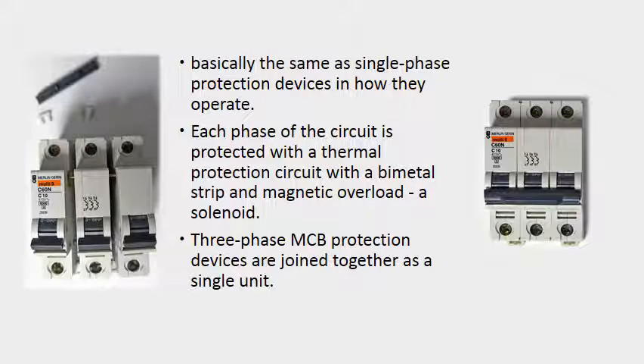So three-phase circuit breakers are basically the same as single-phase circuit breakers. They have the same protection for each phase, but there's three of them. Each phase is protected with a thermal protection circuit, which has a bimetal strip, and it also has a magnetic overload with a solenoid. They're joined together as a single unit, and if you have a look here in this photo, there's a tripping mechanism which is common to all three.